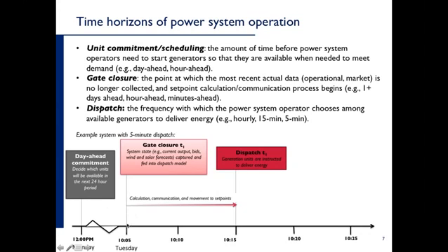We say, what is the demand? What is the wind doing? What is the solar doing? What are all the generators doing? And where do we think the system is going to be 10 minutes from now? So we have a very short-term forecast, basically a 10-minute forecast. At that point, we start our computer calculating the economic dispatch that would be consistent with our short-term forecast of where the system is going to be at 10:15.